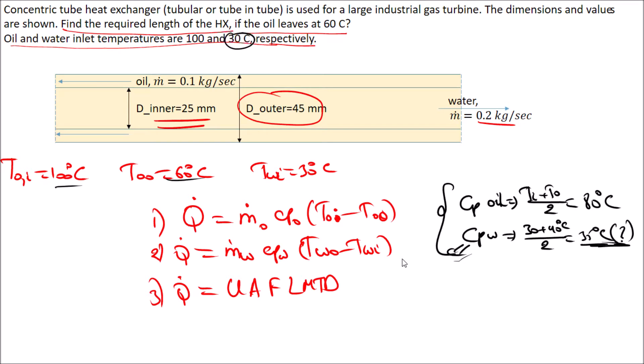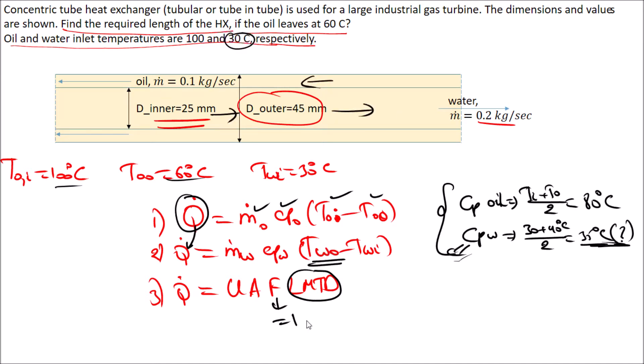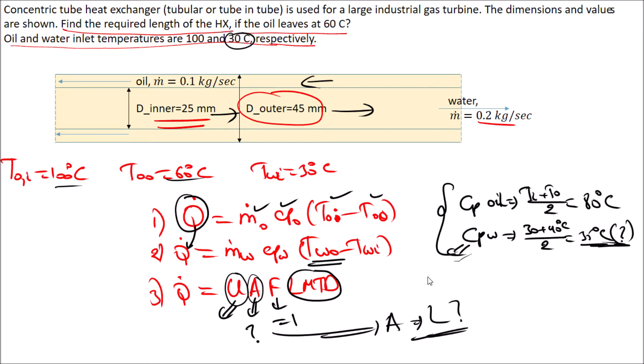We will solve the problem in Excel. We know m-dot for oil and will find Cp from a table. We calculate Q-dot from the oil side, then substitute back to find the water outlet temperature. LMTD is computed next; F equals one for a counter-flow heat exchanger where fluids move in opposite directions. From Q = U·A·F·LMTD, we find the area and then the length.